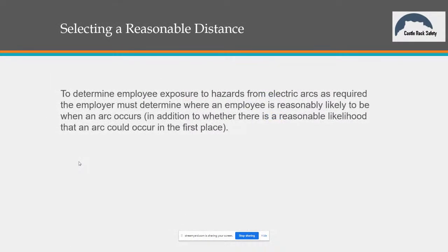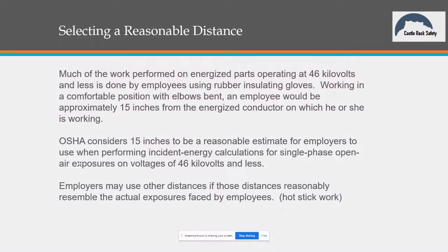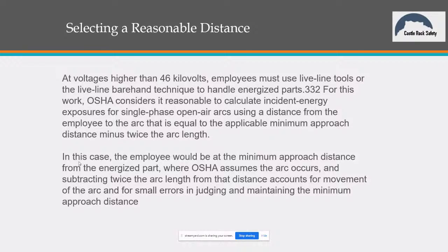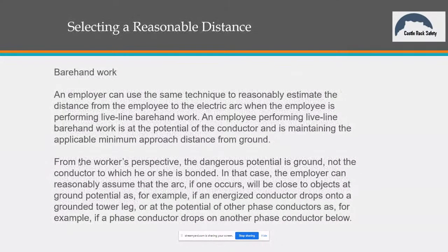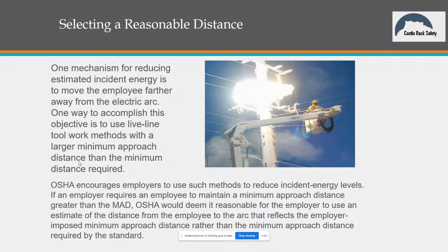Well, and it makes a lot of sense because it looks like you could mitigate that risk by disconnecting at the gate where you're out in open air, and then your electrically safe work condition is over in the actual gear side. Correct. Where you have the more risk, you're mitigating that hazard by ensuring an electrically safe work condition, using the lower risk of the open air. Yep. Makes sense. Correct.